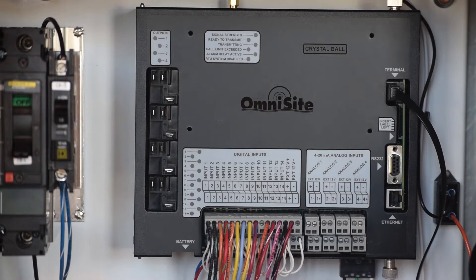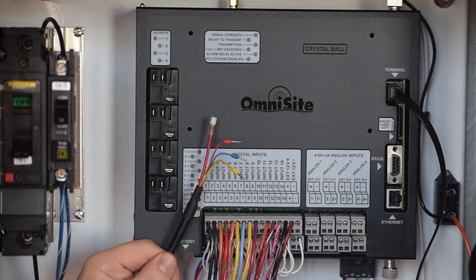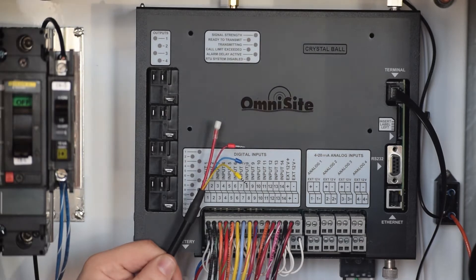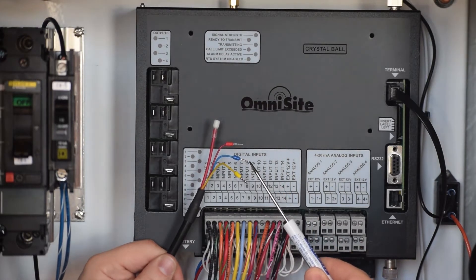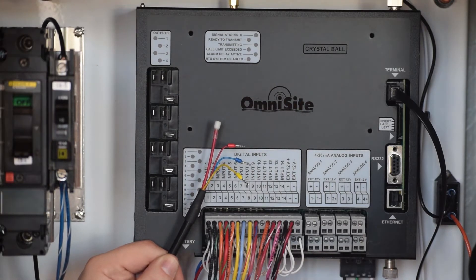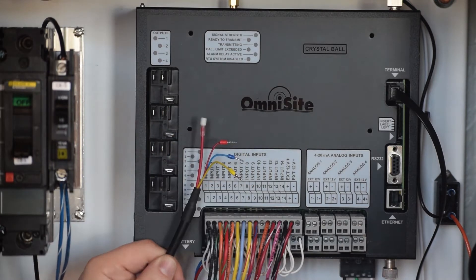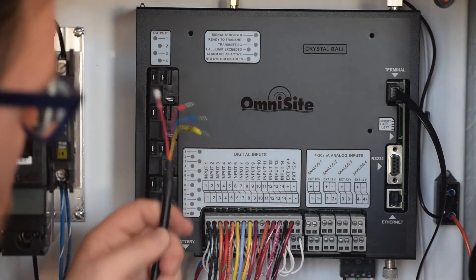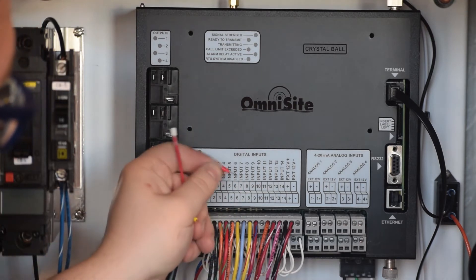You are now ready to wire up your 4 to 20 milliamp level transducer into analog input 1. The OmniSite transducer has a red power lead, a blue signal lead, and a yellow shield lead. You will also notice a breather tube, which is designed to allow the sensor to operate properly. The OmniSite level transducer is a 2-wire loop-powered device.